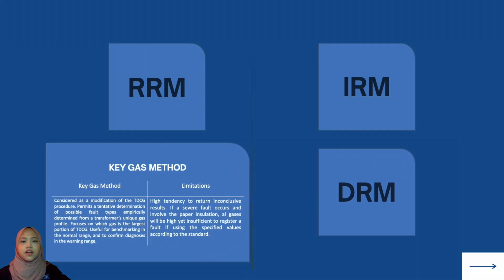Lastly, the key gas method. The key gas method, considered a modification of the TDCG procedure, permits tentative determination of possible fault types empirically determined from a transformer's unique gas profile. It focuses on which gas is the largest portion of TDCG, useful for benchmarking in the normal range and to confirm diagnosis in the warning range. The limitation is a high tendency to return inconclusive results. If a severe fault occurs and involves the paper insulation, all gases will be high yet insufficient to register a fault if using the specified values according to the standard.